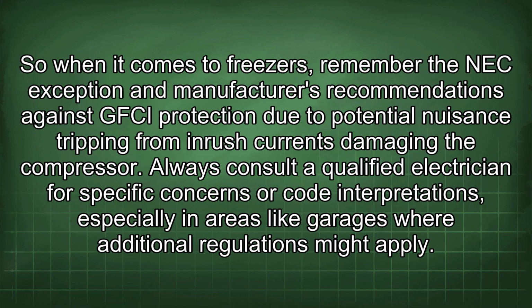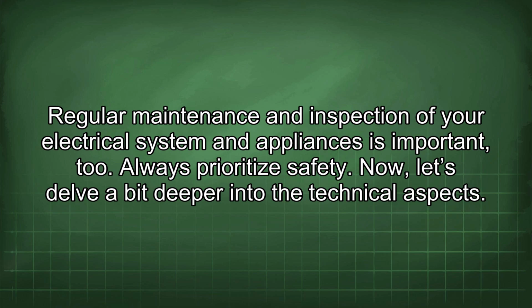So when it comes to freezers, remember the NEC exception and manufacturer's recommendations against GFCI protection due to potential nuisance tripping from inrush currents damaging the compressor. Always consult a qualified electrician for specific concerns or code interpretations, especially in areas like garages where additional regulations might apply. Regular maintenance and inspection of your electrical system and appliances is important too. Always prioritize safety. Now let's delve a bit deeper into the technical aspects.